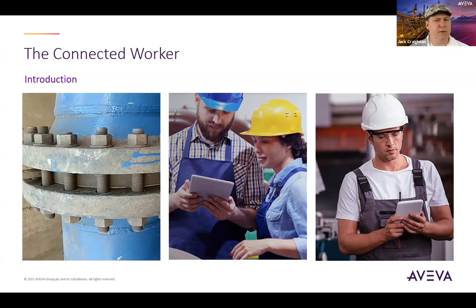Scenario two continues with the same equipment, now entering the startup phase. All locks and tags have been removed, and isolation points are in their normal startup positions. Multiple operators take various roles collaborating on startup procedures, each with their own piece of paper or from a single document, diligently working through the steps. They converse with each other and the board operator over the radio to put the equipment online. Then without any notice, the machine shuts down and multiple alarms start showing on the outside alarm console. It was discovered that the version of the startup procedure they were using didn't match, which caused the safety instrumented systems to shut down the machine. Again, time was lost and startup was delayed for a second time.